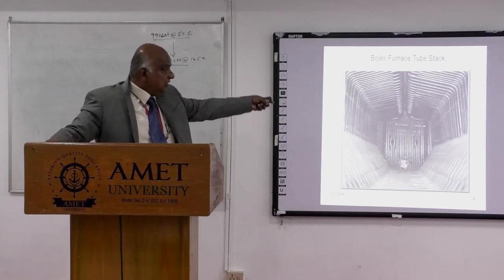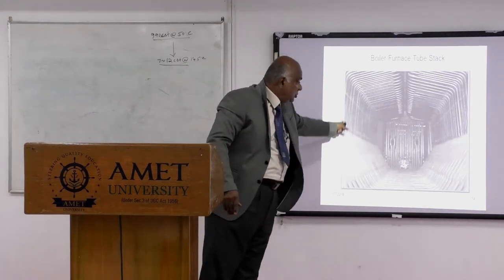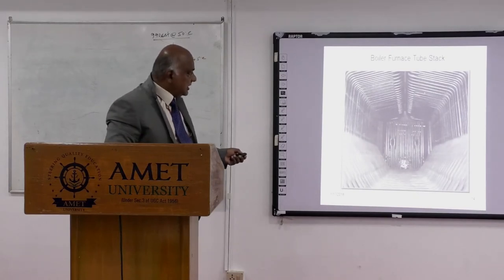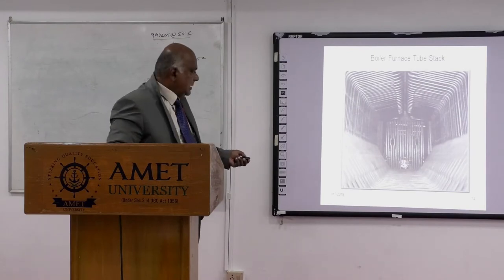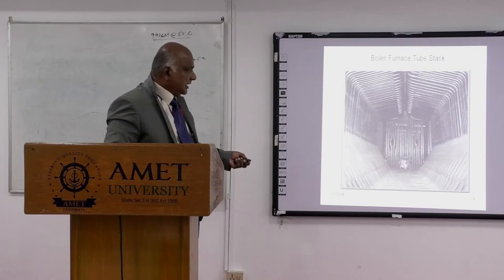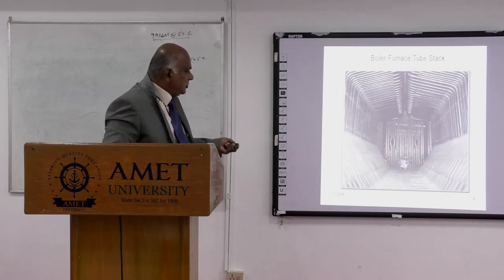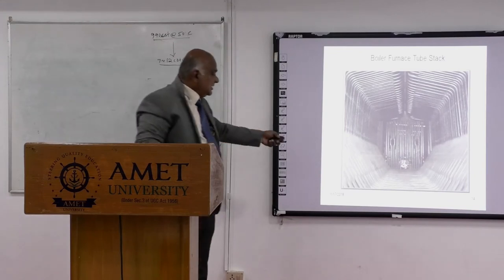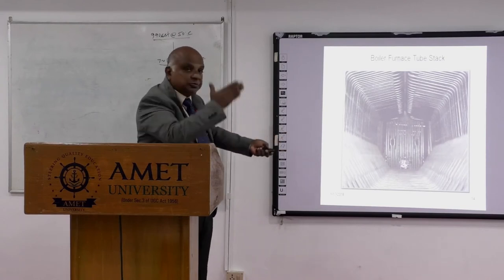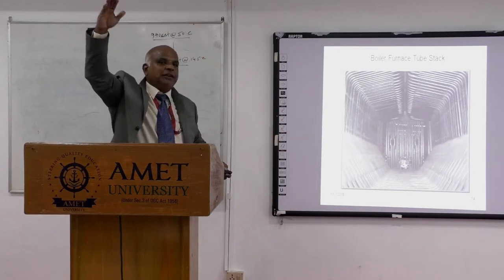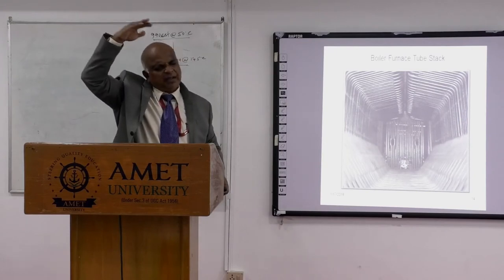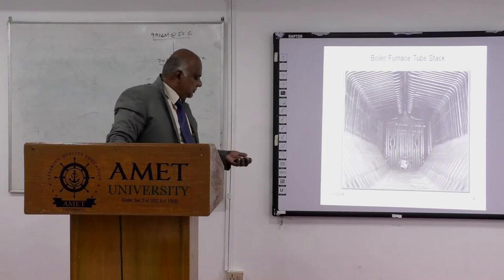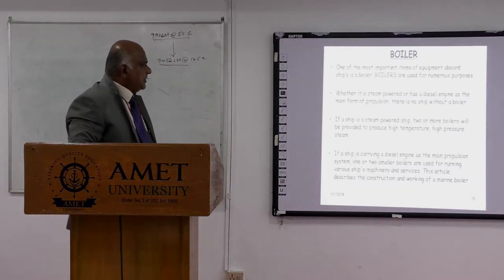For such a steamship boiler, the furnace space is large with multiple burners — about four burners — and some ships use a roof deck burner system. Horizontal burner arrangements are used and the water tubing itself forms the furnace. The flue gas from burning passes through these tubes, then goes to the superheater, economizers, and air preheater for large boilers like the Foster Wheeler.